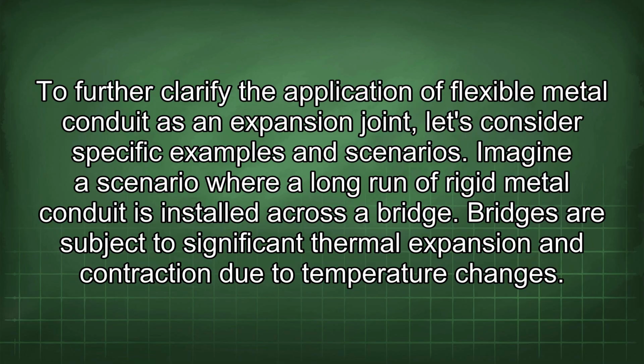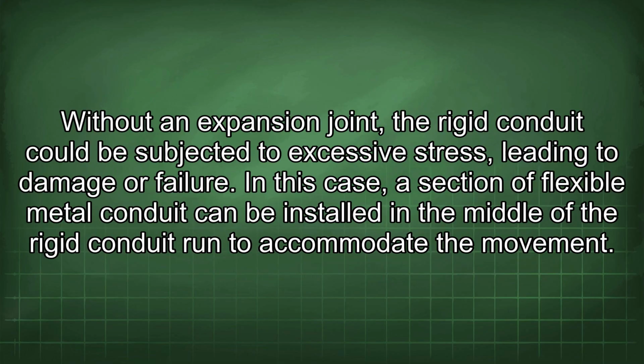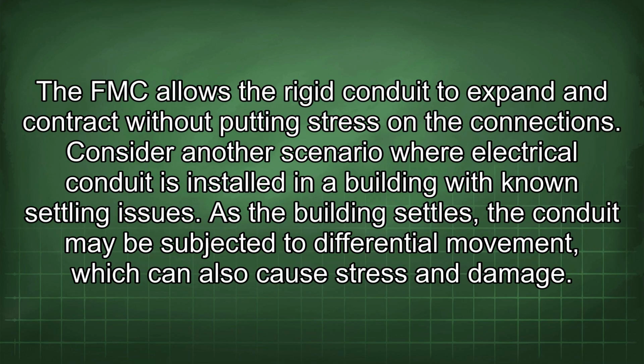To further clarify the application of flexible metal conduit as an expansion joint, let's consider specific examples and scenarios. Imagine a scenario where a long run of rigid metal conduit is installed across a bridge. Bridges are subject to significant thermal expansion and contraction due to temperature changes. Without an expansion joint, the rigid conduit could be subjected to excessive stress, leading to damage or failure. In this case, a section of flexible metal conduit can be installed in the middle of the rigid conduit run to accommodate the movement. The FMC allows the rigid conduit to expand and contract without putting stress on the connections.